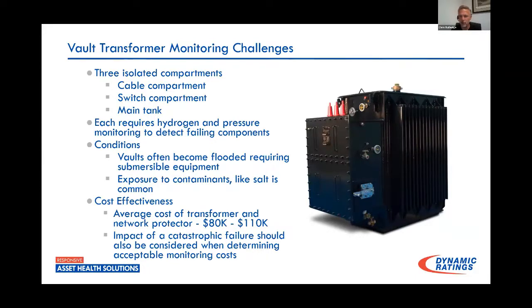But when you get down to these smaller transformers that may not be rated for that level of vacuum, there's really no way to dry them out. So my thought process is, I would rather prevent the moisture from the beginning and avoid that moisture ingress, rather than worry about it on the tail end of, okay, now what am I going to do about it? Because again, I've untanked, I've tried drying in ovens, I've run the offline dry out systems for 6 months, and all of this does help, but I've never really been able to get one back to a good dry state after that moisture ingress has happened.